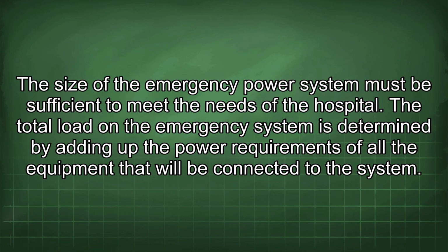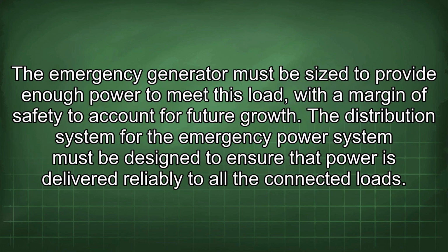The size of the emergency power system must be sufficient to meet the needs of the hospital. The total load on the emergency system is determined by adding up the power requirements of all the equipment that will be connected to the system. The emergency generator must be sized to provide enough power to meet this load, with a margin of safety to account for future growth. The distribution system for the emergency power system must be designed to ensure that power is delivered reliably to all the connected loads.